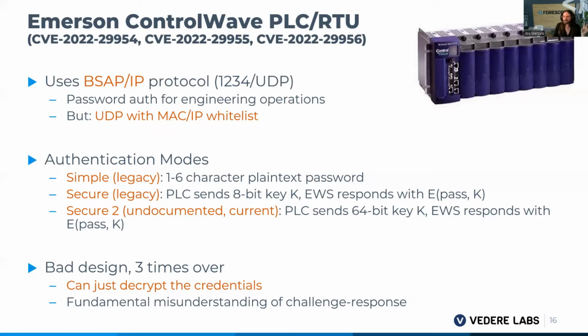Currently they are using secure mode 2, which is undocumented, but it's essentially the same as secure mode, except with a bigger key and a different algorithm. Now the PLC sends you a 64-bit key, you encrypt the password, and send it back to the PLC again. This is fundamentally bad design, 3 times over, and it speaks to a fundamental misunderstanding of how a challenge response mechanism is supposed to work. This could have been addressed twice, once when you introduced secure mode, then when you introduced secure mode 2, but it wasn't done. So unfortunately, 2 missed chances.